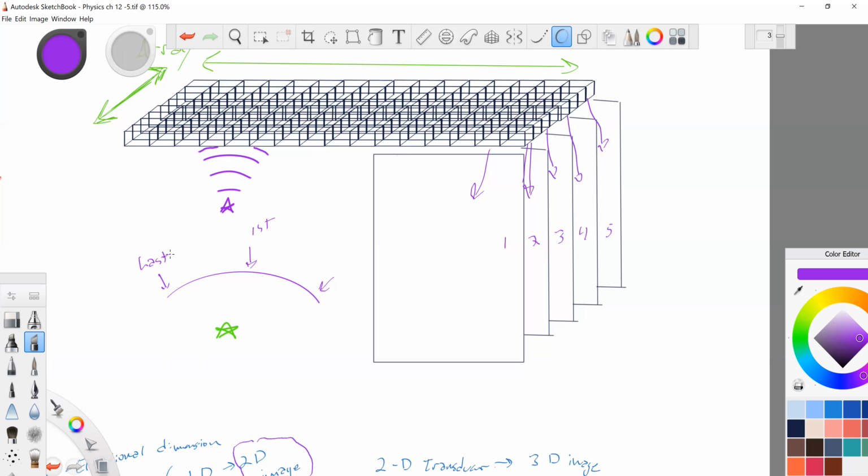And so inside the computer system, it says, you know what? This wasn't a round object creating this. This was a flat object, or in this case, a star, that created a rounded echo. But the fact that it was a rounded echo, that's just the way sound moves normally when it's bouncing around. And so we phased the receive echoes. Just as we phase the transmitted sound, we're actually able to phase the received echoes.